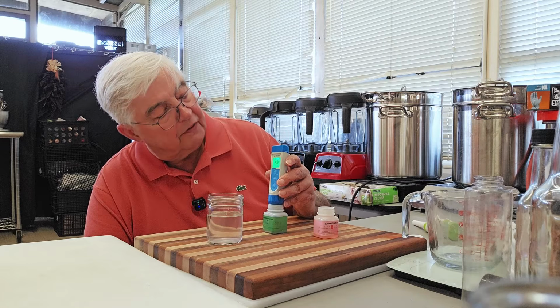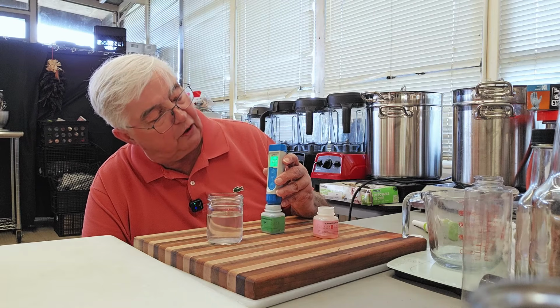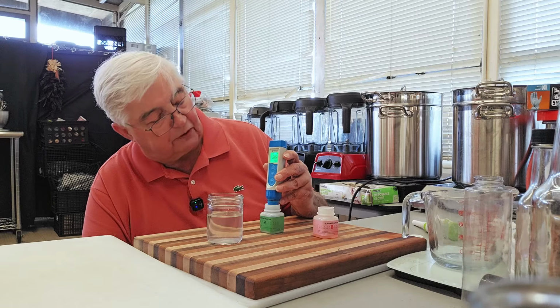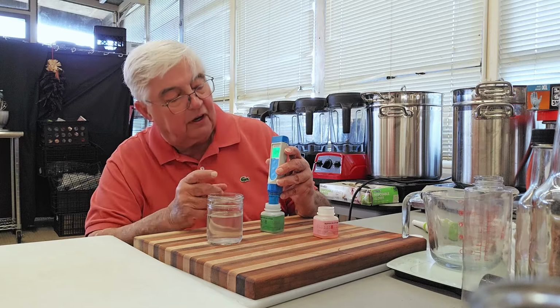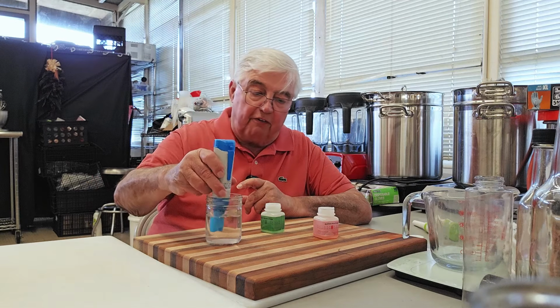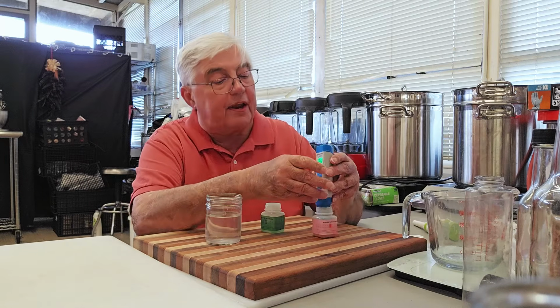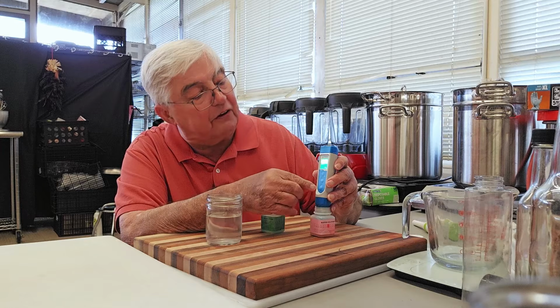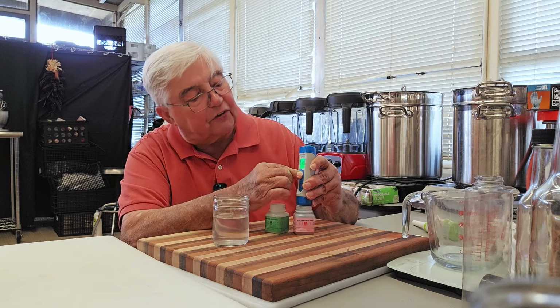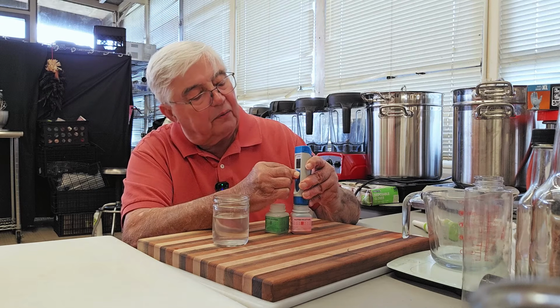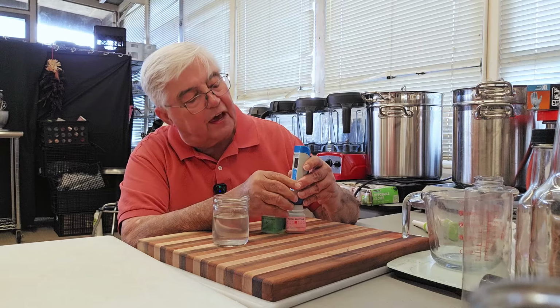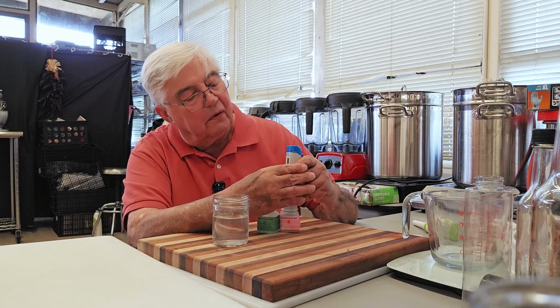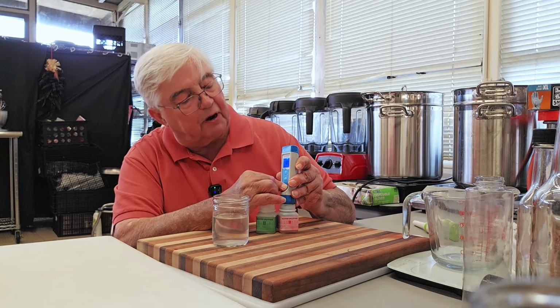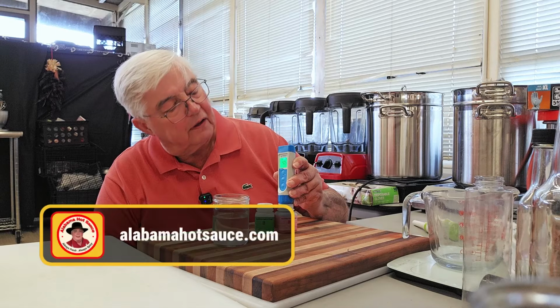On the Apera, the number doesn't blink, but down below there's a little smiley face that pops up once this meter is successfully calibrated. There you go. We see our smiley face. We're now calibrated at the 7.0 level. We rinse it off, and we go to the 4.0. We give it a second to stabilize so it figures out what kind of solution it's in. You have to turn it off and turn it back on. So I'll do that. And then you push the calibration button. You go into calibration mode, the little smiley face pops up, and the 4.0 is calibrated, okay? And that's all there is to it, folks.